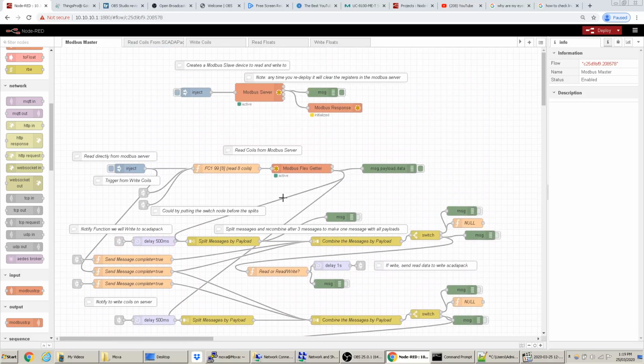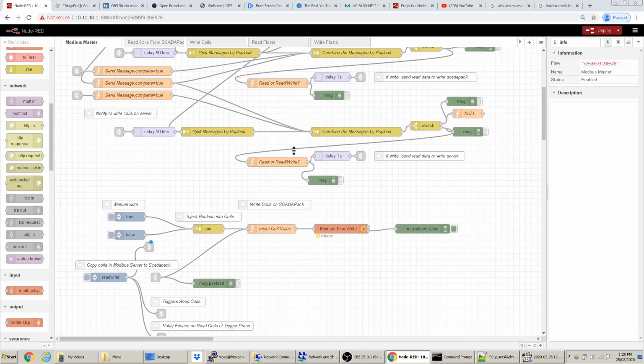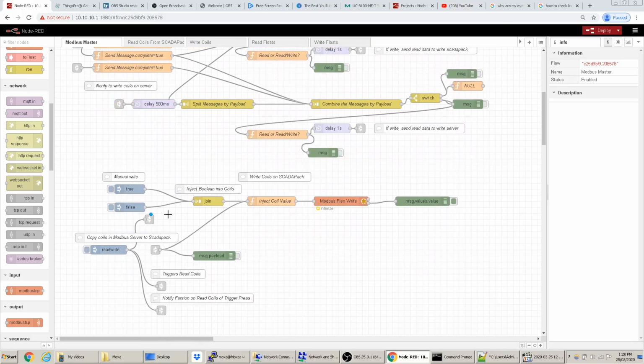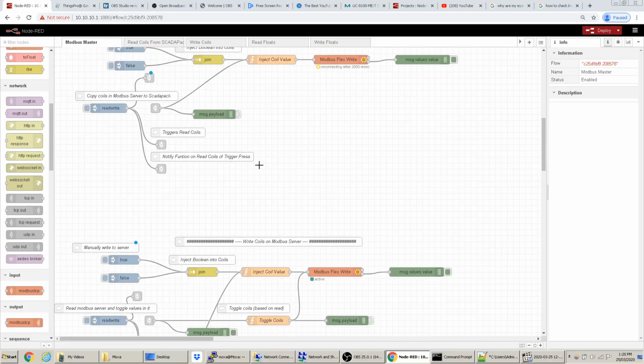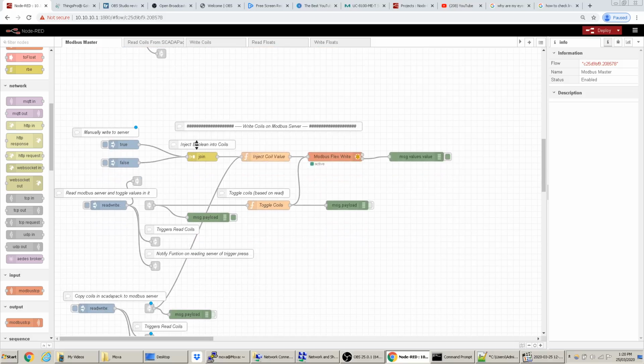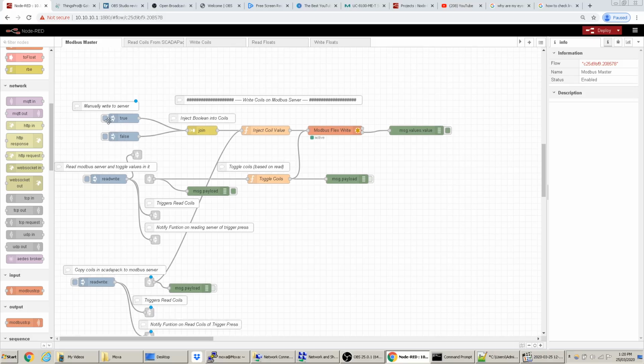So just a little recap of what we're able to do. We're able to read from the Modbus server, just read. We're also able to write to the Scadapack manually. We're able to copy coils in the Modbus server to the Scadapack, and remember, the Modbus server is something Cygnet can send data to, so that data can be passed to the Modbus server and then to the Scadapack. The other thing we can do is manually write to the server.